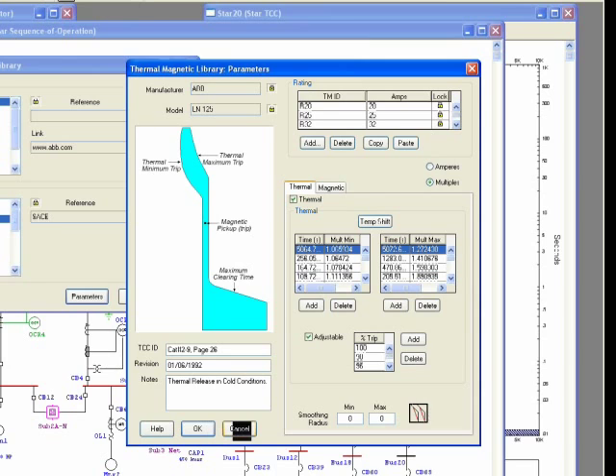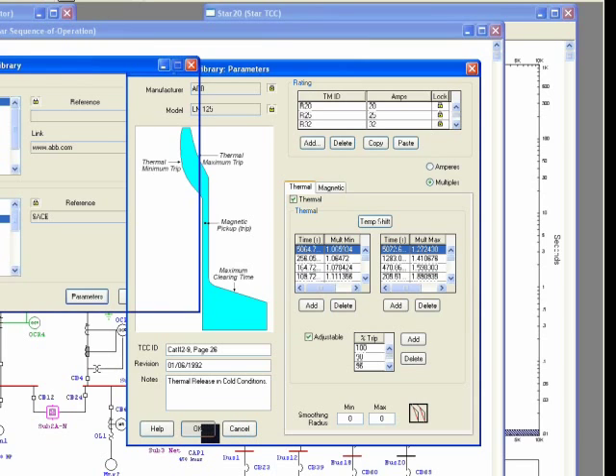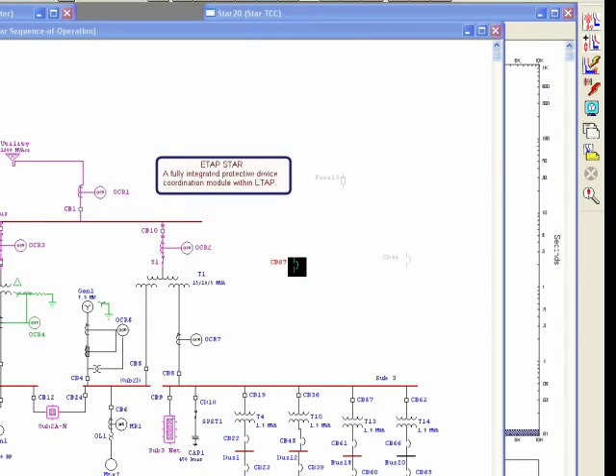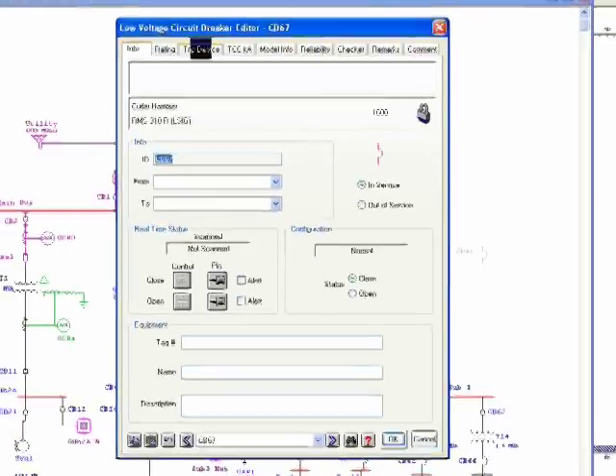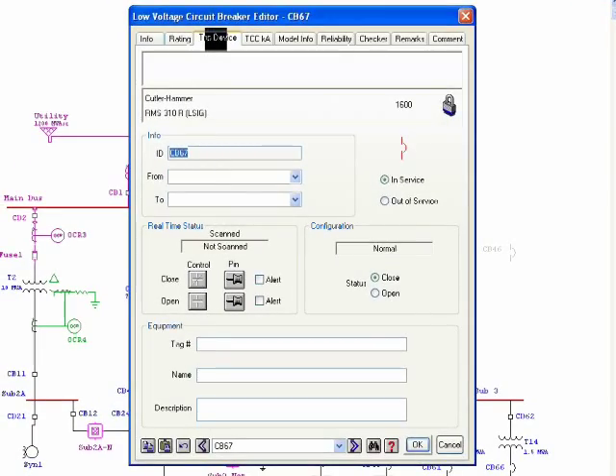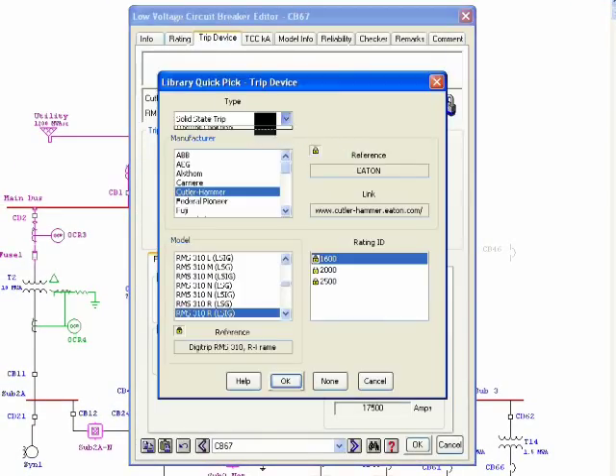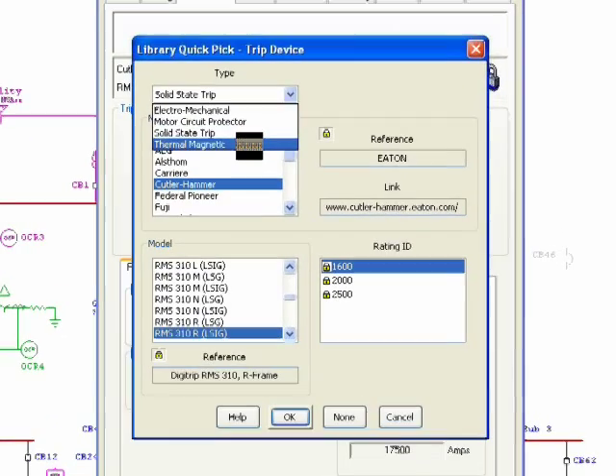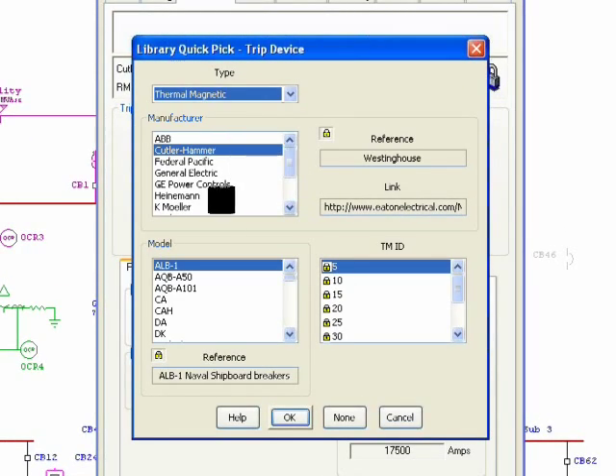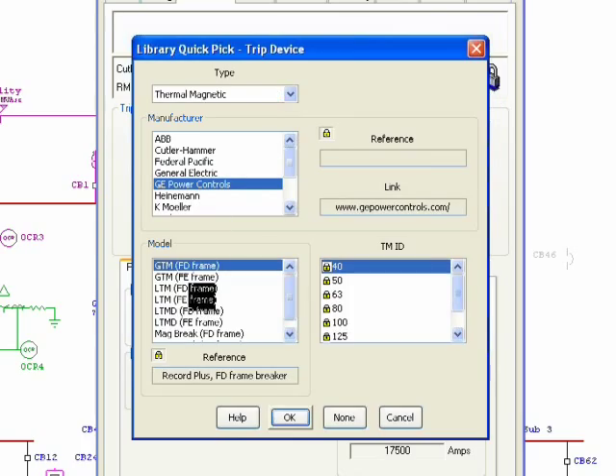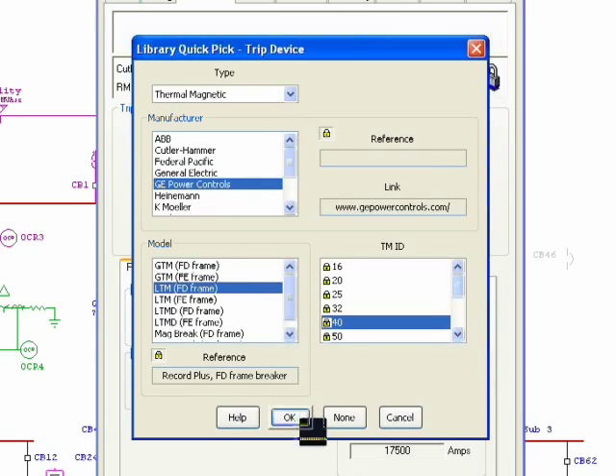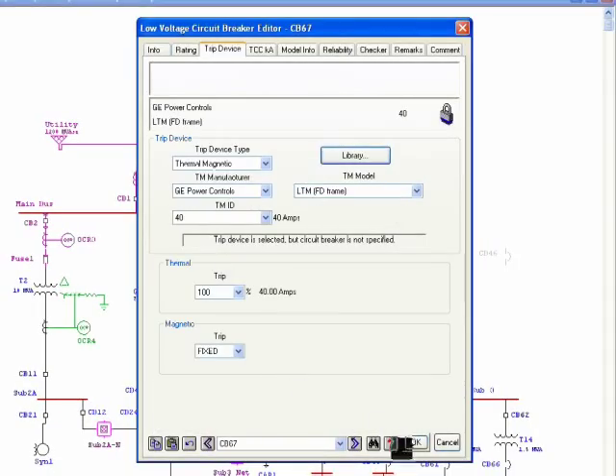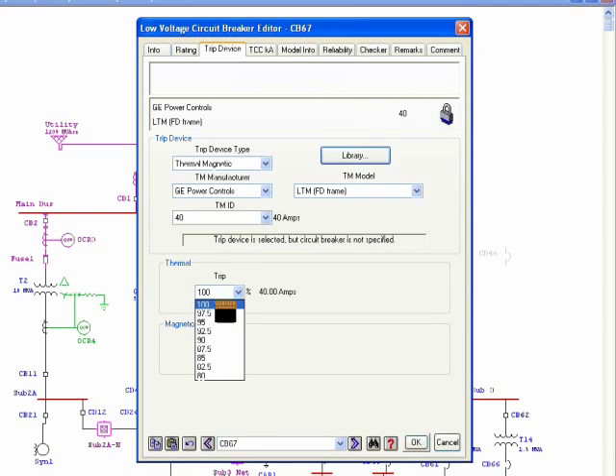The next thing I'm going to talk about is if I go to the breaker, select trip device, I can go to the library and select thermomagnetic from this list. In this list I have, for example, GE Power Control, and this is one of the existing models that I have.